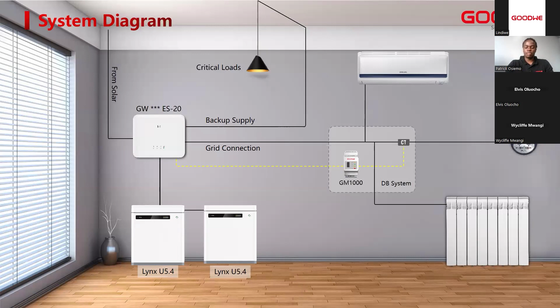And on the output side, you get to terminate already segregated loads. We have two AC ports for the backup loads. These are critical loads. And on the AC side, we also have the on-grid port, where you connect the non-critical loads. And given that it can be linked to the grid, the ES20 comes with a smart meter within the package, already pre-wired with CTs. This allows you to do zero export monitoring and load monitoring, as well as monitoring the generation and consumption of power through the grid incoming lines.